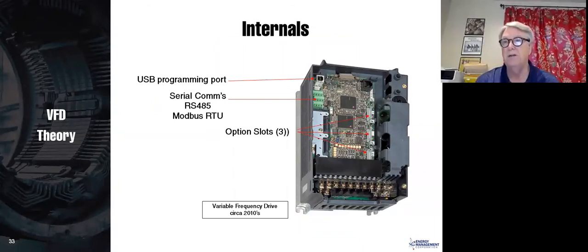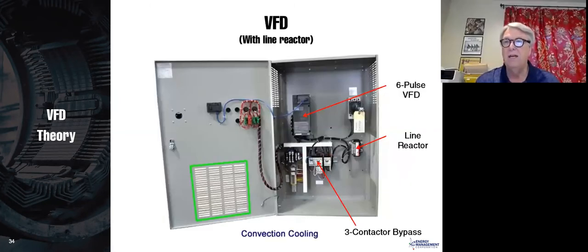All that circuitry is now surface mount, and it's got 2 very high-speed microprocessors. We would call them digital signal processors because they're built specifically for variable frequency drives. And this drive will run circles around the other one because of the incredible advances in solid-state microprocessors. But other than the microprocessor, this drive works the same way as it did in 1987. I find that fascinating that there really haven't been any significant advances in variable frequency drive topology, for low voltage at least, since 1987. Here's a drive in an enclosure.